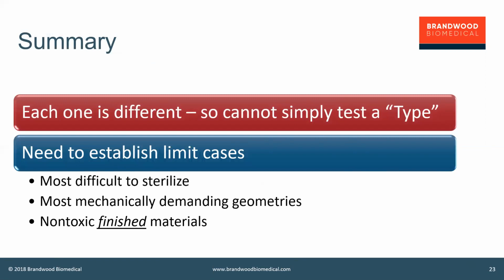Look for the physical configuration, size, shape, porosity, cavities, etc., that makes it the device most difficult to sterilize, and test that. Make that your test case and run that through a sterility validation program, because that will validate all of the less difficult ones as well. Look at the most mechanically demanding geometries when you're thinking about the mechanical integrity of your device, and validate that. And then for biocompatibility, you are looking to demonstrate that you have non-toxic finished devices, that the materials in the finished form are non-toxic, preferably by chemical characterization, but possibly also by biological evaluation.